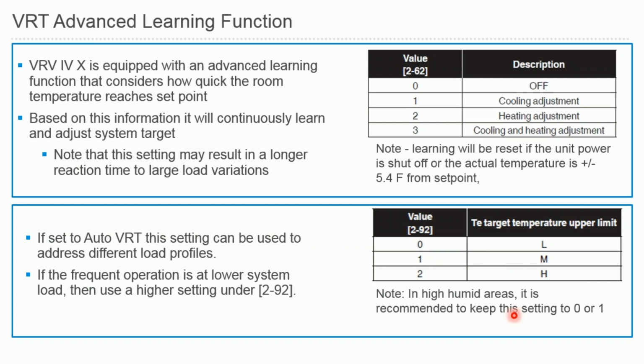Another set of field settings for VRT, that's for VRT Auto as well. Again, you will have 3 different settings for your maximum TE target temperature, your upper limit. You have low, medium, and high. The default setting will be medium. So our recommendation is, if you are sizing your outdoor unit based on heating, especially in cold climate applications, the chances are your unit will be oversized in cooling mode. And in those scenarios, we recommend choosing high H for your target TE upper limit, so you can get higher efficiency out of your system.